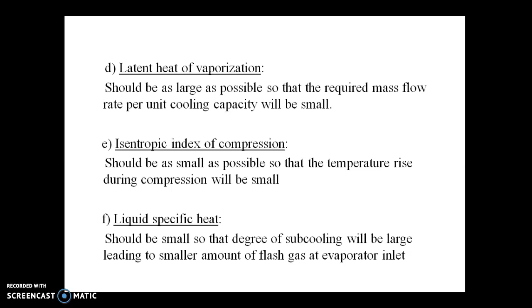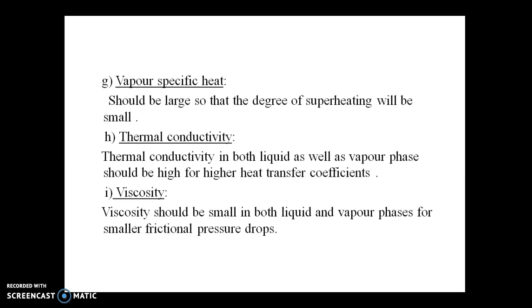The next one is the liquid specific heat. It should be small so that the degree of subcooling will be large, leading to smaller amount of flash gas at evaporator inlet. Vapor specific heat of refrigerant. This value should be large so that the degree of superheating will be small. The next one is thermal conductivity of the refrigerant. The thermal conductivity of the refrigerant in both liquid phase as well as vapor phase should be high for high heat transfer coefficients. The next one is the viscosity of the refrigerant. Viscosity of the refrigerant should be small in both liquid and vapor phases for smaller frictional pressure drops.